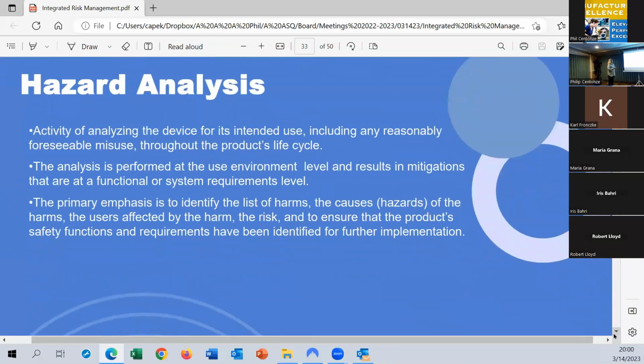So hazard analysis is a little bit like an FMEA, but at the system level, right? And this is where we use the terminology of sequence of events and hazardous situations. And we try to identify anything that's foreseeable, right? Including foreseeable misuse at the system level that could result in hazard.